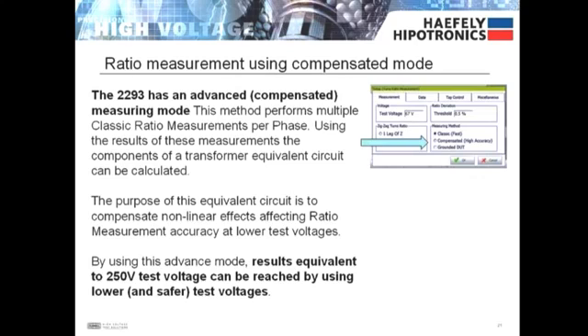The 2293 implements an advanced compensated measuring mode where it performs several pre-checks to determine the transformers real RLC properties and compensates for these nonlinear properties to provide highly accurate results. By using this advanced mode, results equivalent to using 250 volt test voltage can be reached by using much lower and safer test voltages.